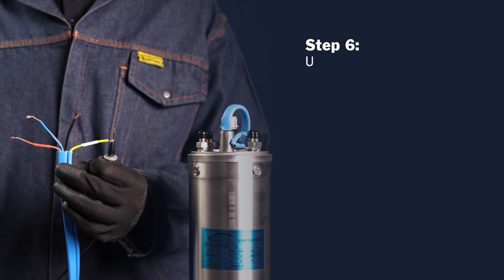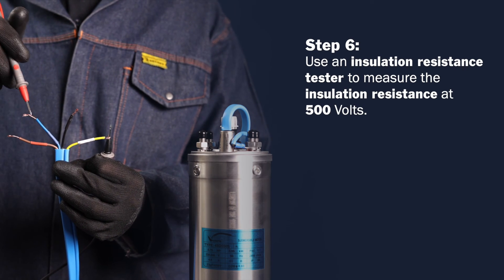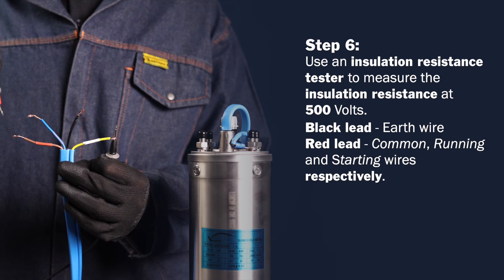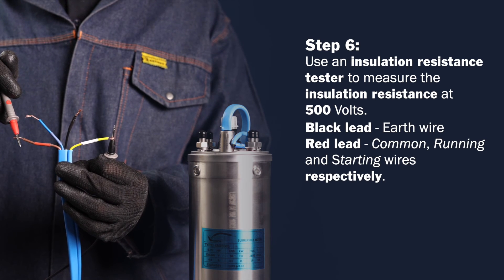Step 6. Using an insulation resistance tester, measure the insulation resistance at 500 volts with the black lead connected to the earth wire and the red lead connected to the common, running and starting wires respectively. The reading should be higher than 1 mega ohm to be acceptable, but in practice, an open line reading should be obtained.